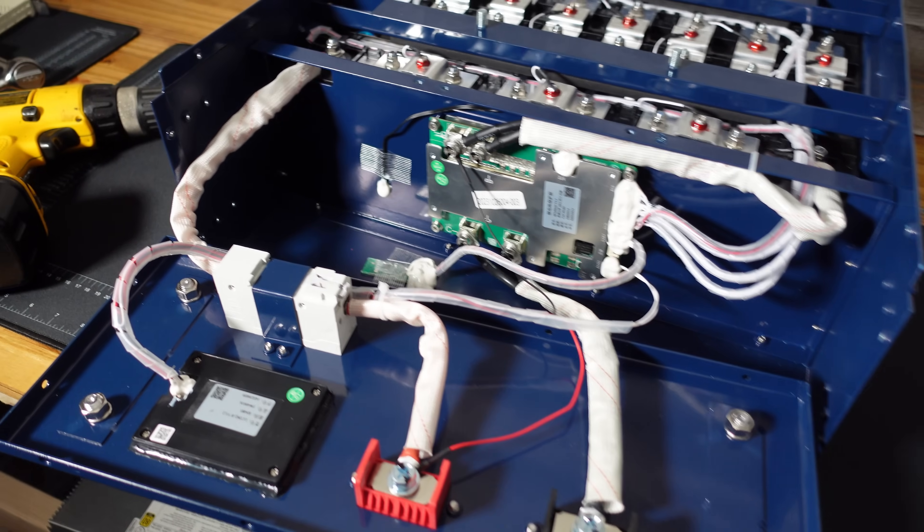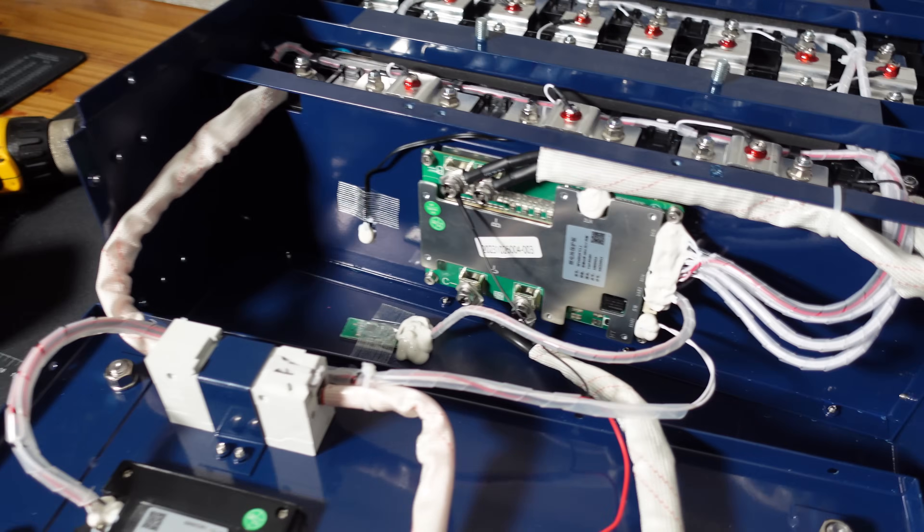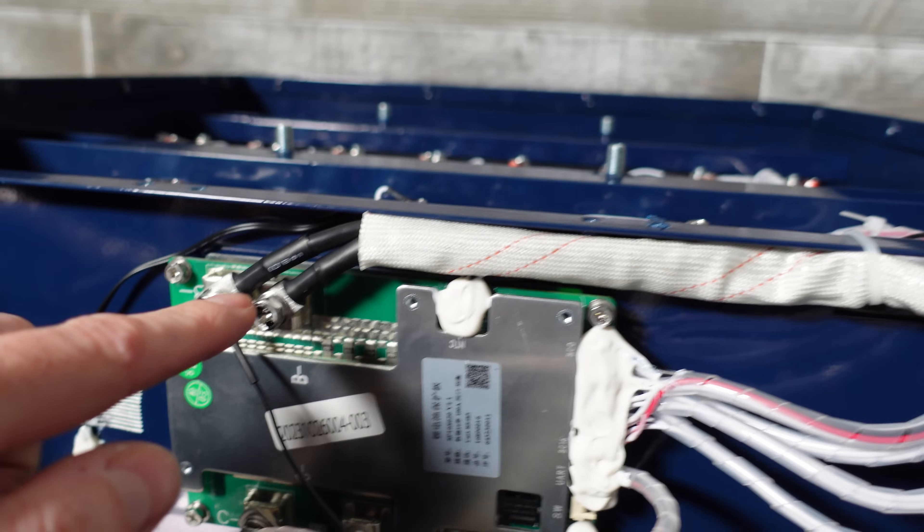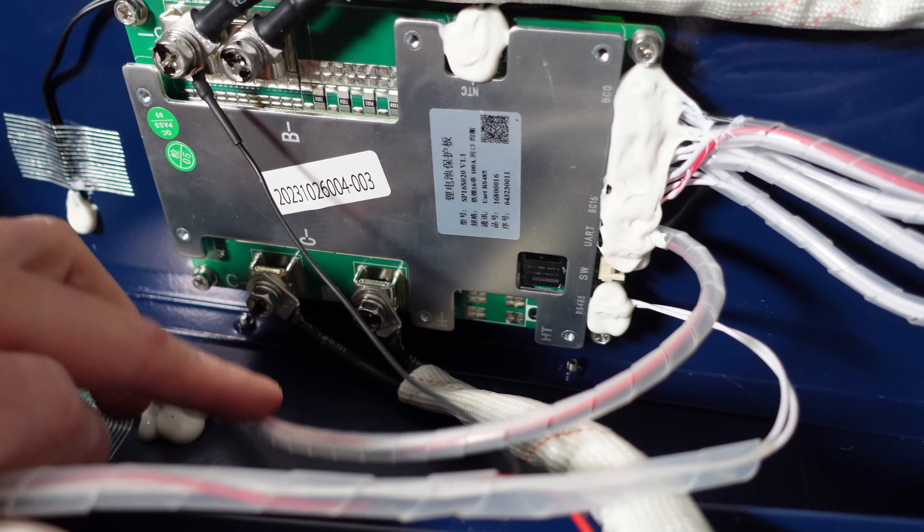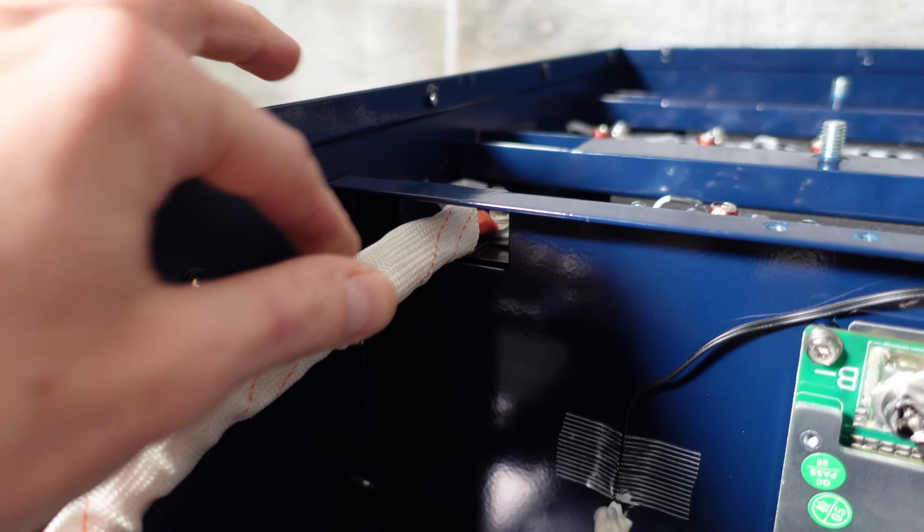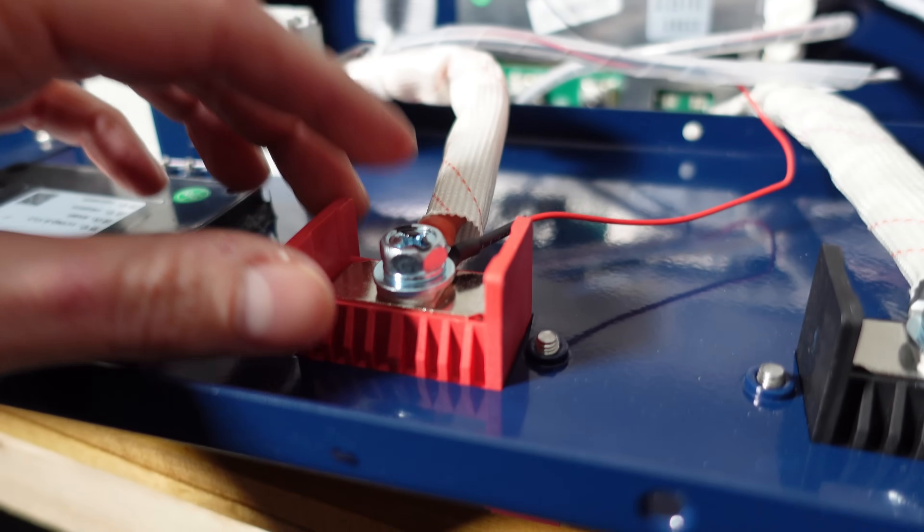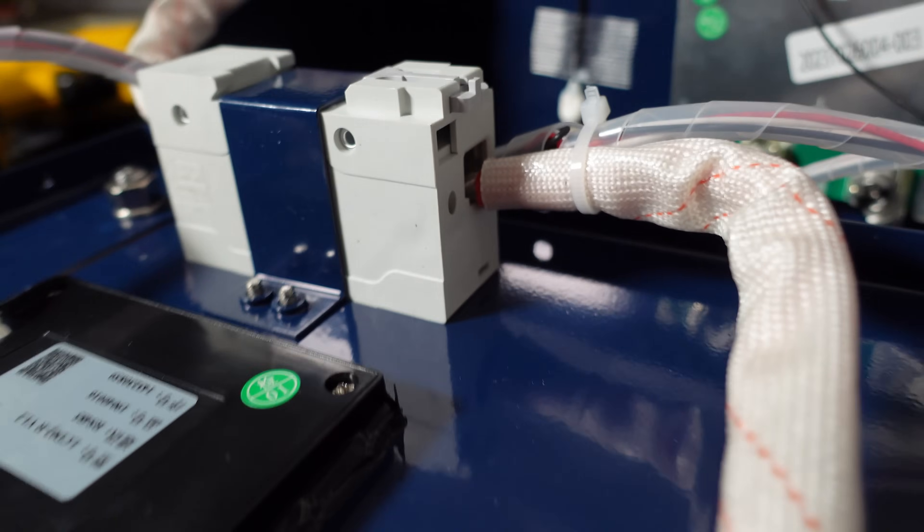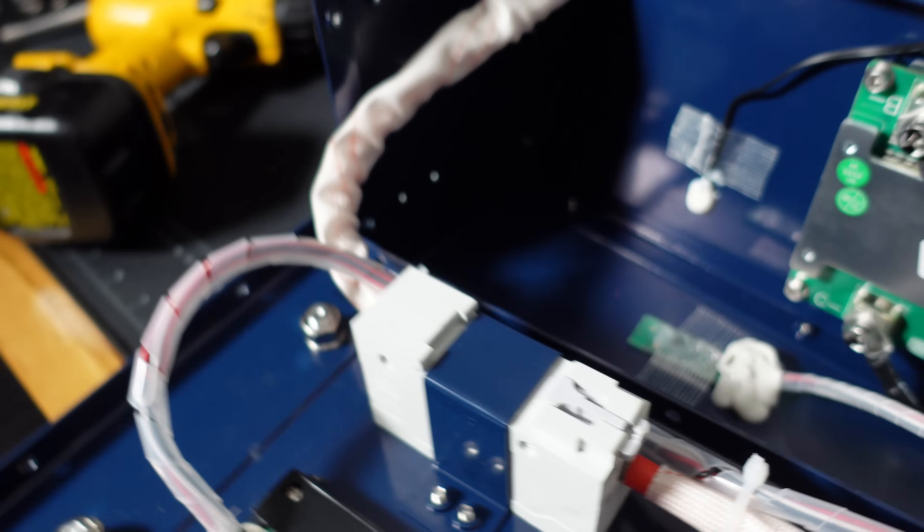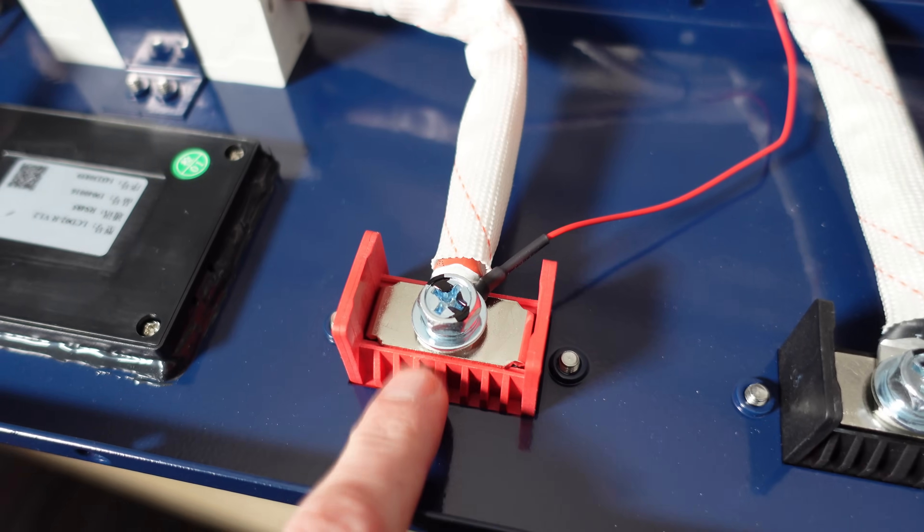So the inside BMS area is very simple. As I've said, it's not a Pace BMS. There's not a whole lot to it. We can see our negative terminal comes off the battery. It's a pair of number eight gauges that goes into the B minus terminal and then we have the conductor coming out of the C minus terminal over to the main negative lug. The positive is a number six coming off the battery. It goes down into the circuit breaker. Then from the circuit breaker it goes over to the main positive terminal and these connections do appear to be good on the circuit breaker. I did pull them and nothing moved on either side. I gave them both a good tug. I do see torque marks on pretty much all of the bolts, which I do like to see. That means somebody has checked them all. They're on the BMS as well and there are torque markings on all of the battery bolts.